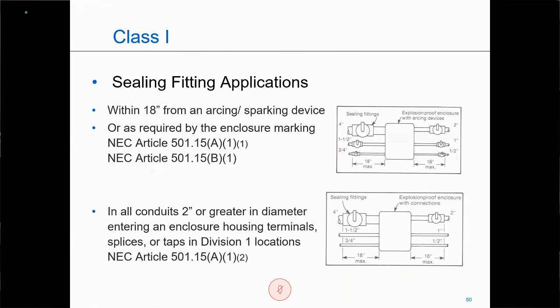This is how they would achieve passing part of the UL 1203 test. So in this particular scenario, if it was listed in the instructions or in their catalog, it would be easy to miss that the sealing fitting needed to be in a position that was closer than the 18 inches. So now it's required to be marked on the nameplate, right on the enclosure, so the installer knows that that sealing fitting needs to be in a different position on that particular enclosure.